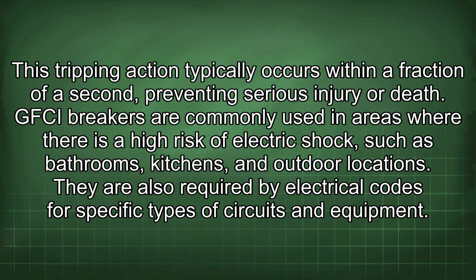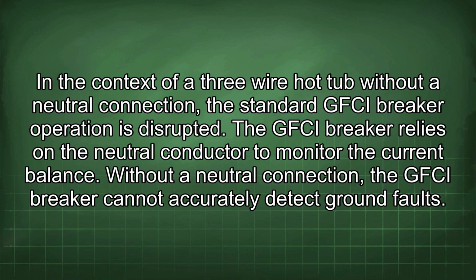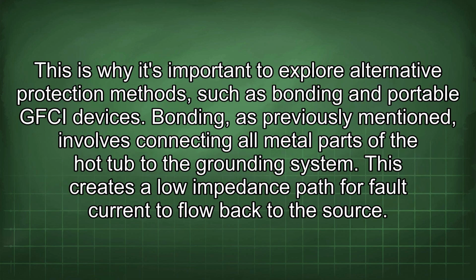GFCI breakers are commonly used in areas where there is a high risk of electric shock, such as bathrooms, kitchens, and outdoor locations. They are also required by electrical codes for specific types of circuits and equipment. In the context of a 3-wire hot tub without a neutral connection, the standard GFCI breaker operation is disrupted. The GFCI breaker relies on the neutral conductor to monitor the current balance. Without a neutral connection, the GFCI breaker cannot accurately detect ground faults. This is why it's important to explore alternative protection methods such as bonding and portable GFCI devices.